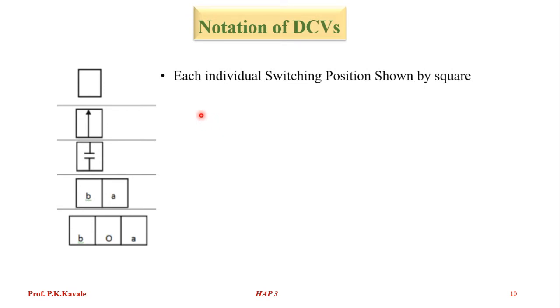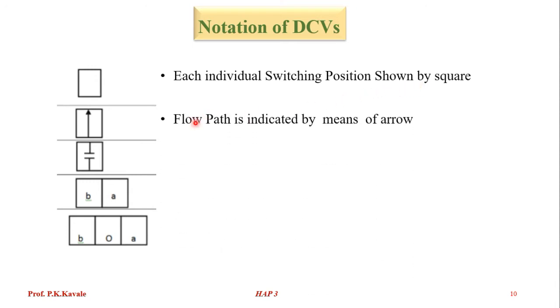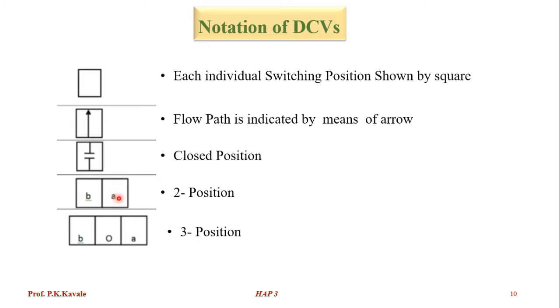Regarding notation for DCVs: each DCV or any valve can be represented by a square. Each individual switching position is shown by a square. Flow path is indicated by an arrow. A closed position means it does not allow flow from one port to another port. If there are two squares, it means two positions; if there are three squares, it means three positions.